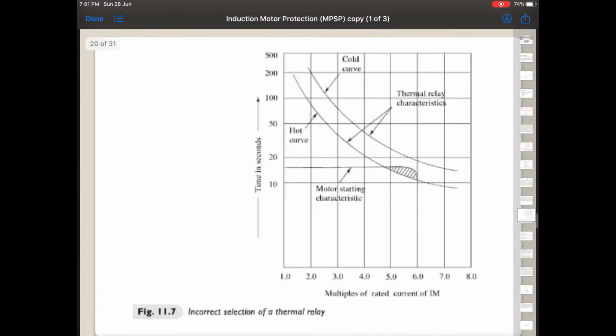And as discussed here, you cannot select a motor starting characteristic which matches or coincides with the hot curve of the relay. So this is the characteristic of a relay, cold curve and hot curve. As was explained earlier, you cannot have a motor characteristic coinciding with it. If so, the motor will not run or start in hot condition, and it will be tripped by the relay. For that reason you go for advanced, that is DSP and microprocessor based relay.